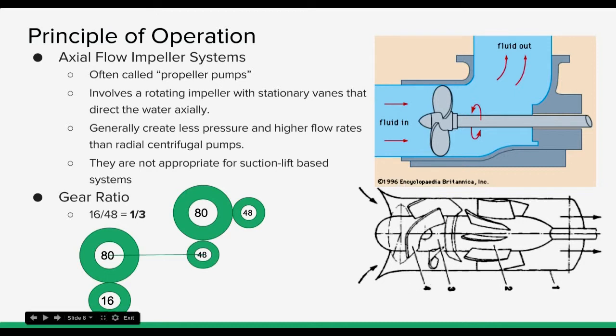These systems involve rotating impellers with stationary vanes that direct the water axially. And as you can see, these are the stationary vanes. And these just direct the water. They don't turn or do anything else except for provide a passage for the water to go through. These generally create less pressure and higher flow rates than the radial centrifugal pumps, which was something that we were looking for and a big factor in why we chose this system.